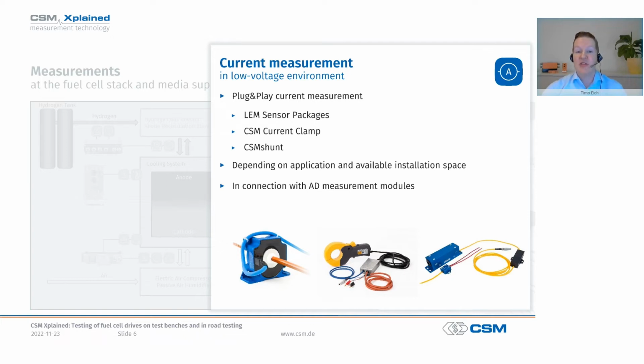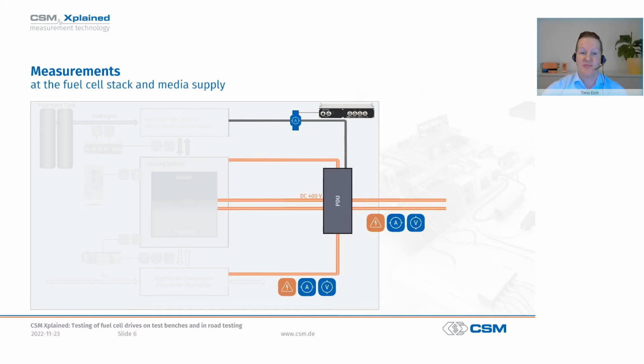And you now simply connect all these sensor packages, for example, to our fast EtherCAT measuring modules. They acquire the current values very dynamically with up to 1 megahertz per channel, because the transients and harmonics are usually very fast processes which we have to sample accordingly with high sampling rates. And because of the high sampling rates and the correspondingly large amount of data, these modules no longer communicate via CAN bus, but with a fast bus system, the EtherCAT.